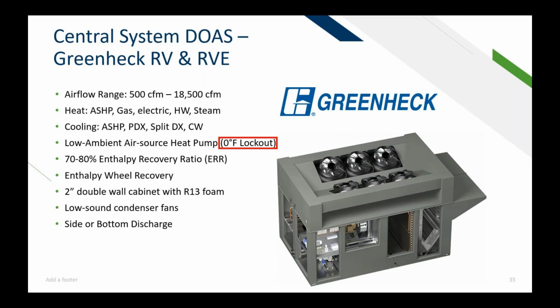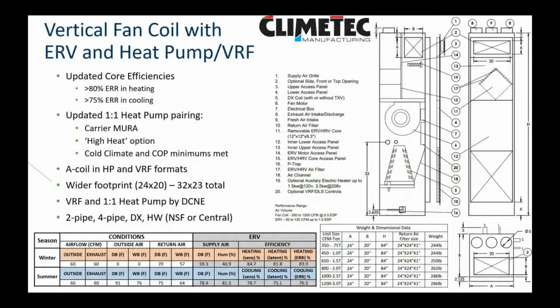But along those lines, if you're working on a system that may not be passive house, consider this as an option. We have a vertical fan coil with ERV and heat pump integrated. This, like I said, wouldn't necessarily be passive house compliant because your ERV module is actually integral to the vertical fan coil, VFC. So, passive house wouldn't like that necessarily because it would be an integrated system. There wouldn't be separate ratings, but this has been a really great option for us.